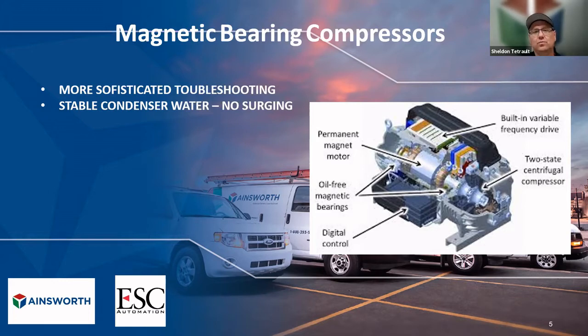It's not really an issue that comes up much anymore due to VFDs on cooling towers. Condenser water flow is typically pretty stable nowadays, but it is something to be aware of, that chillers are part of a system, and having your chilled water system as well as your cooling tower and those pumps all working together really sees some benefits in a building. So surging is tough for these machines.